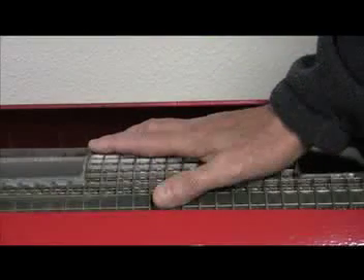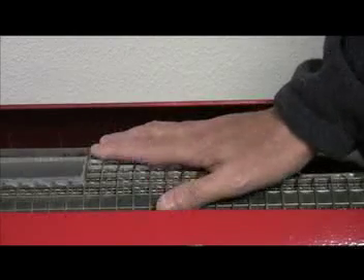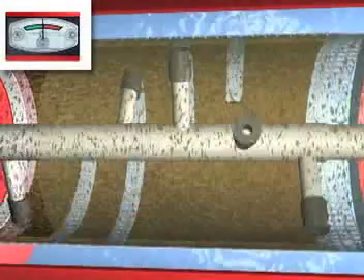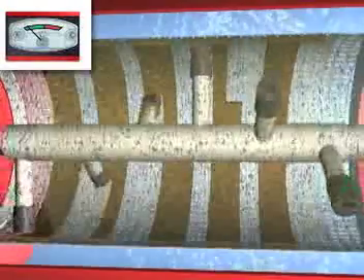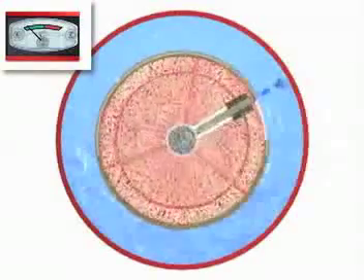This is an SAF 6000 automatic self-cleaning filter. It automatically cleans when it reaches a pressure differential — in this case, on this particular one, of 7 PSI. And when it reaches that differential pressure, a flush valve opens and it automatically back flushes the dirt off the screen, out into the waste stream.